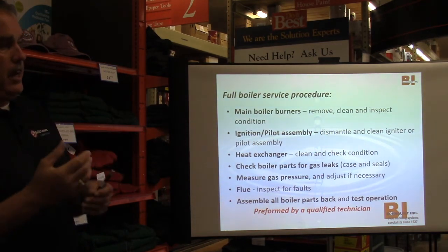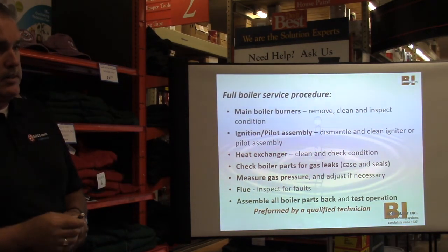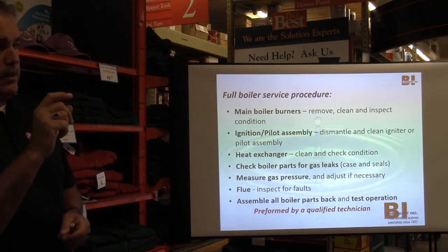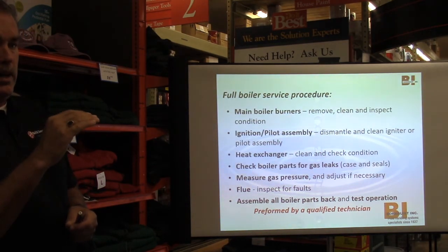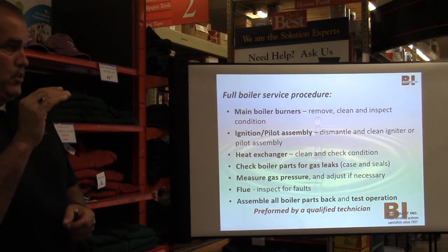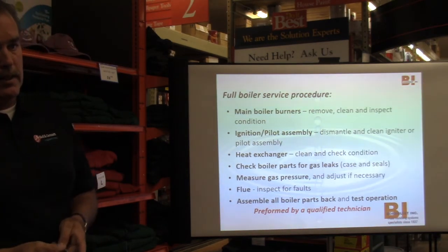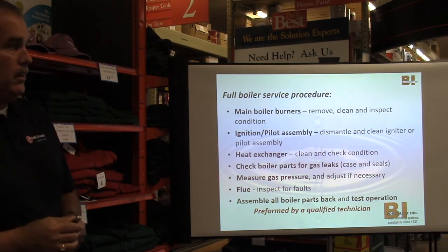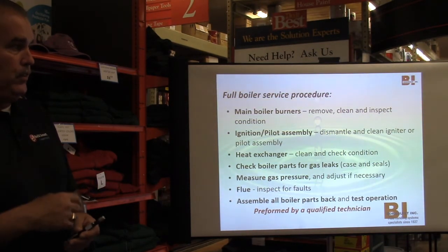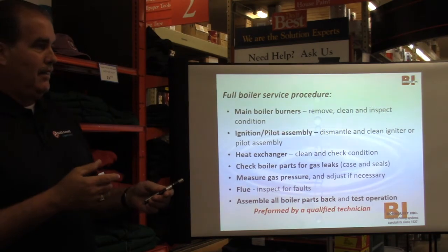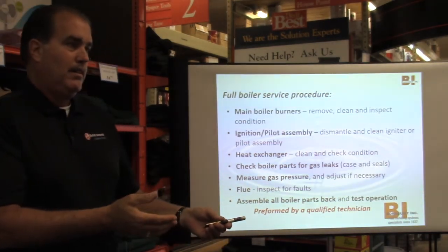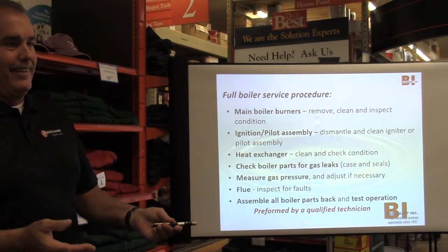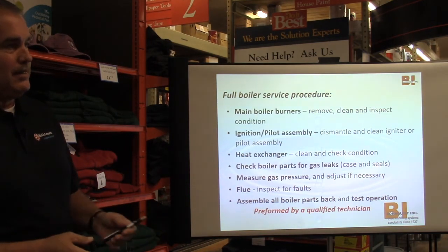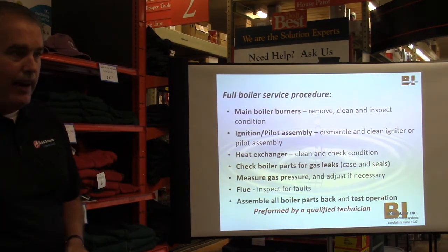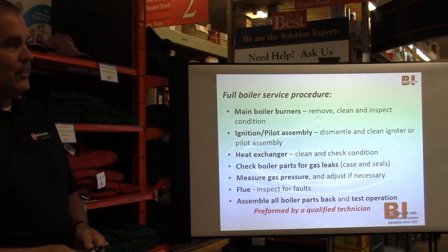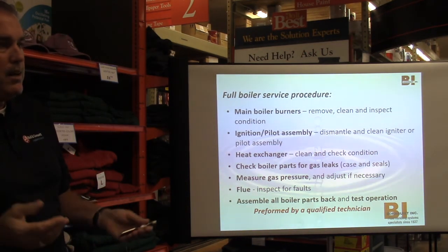The modulating higher efficiency type equipment can handle plastic, but usually they'll make the maximum set point low enough so that they know the flue gas temperature won't get high enough to melt the plastic. And they program that into the boiler to protect it from melting the flue. But if you think about it, they're protecting it from melting the flue. How about just use metal? I mean, the expense, unless you own a high rise and you've got to run it up 30 feet or 30 stories, you're talking a small amount of money.